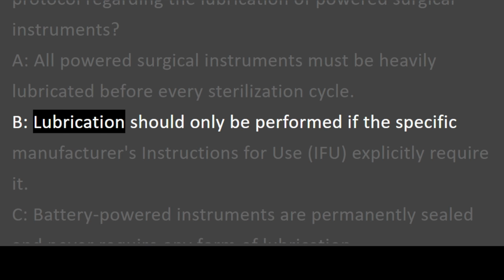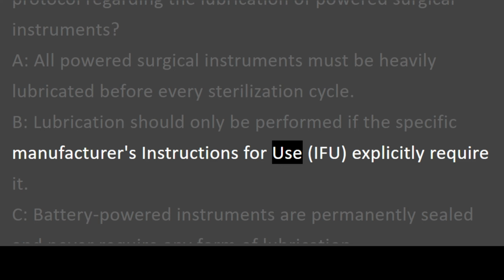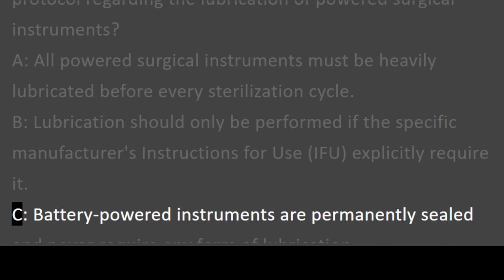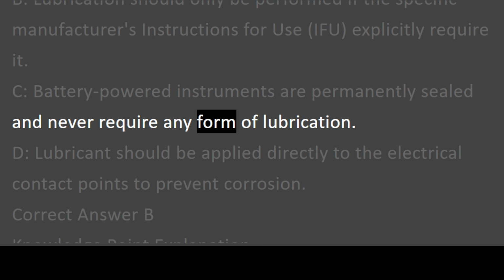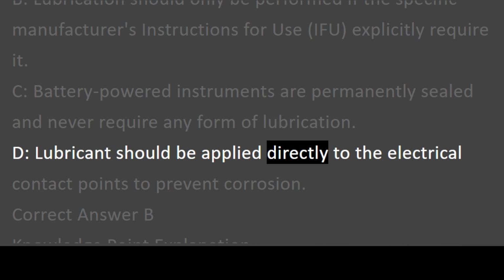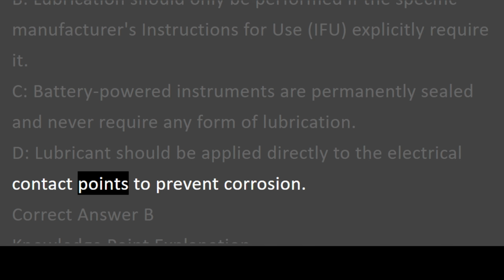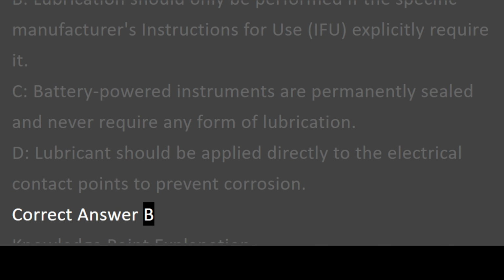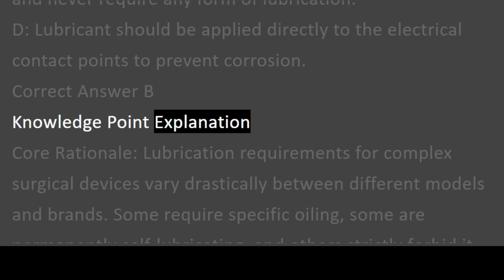B. Lubrication should only be performed if the specific manufacturer's instructions for use, IFU, explicitly require it. C. Battery-powered instruments are permanently sealed and never require any form of lubrication. D. Lubricant should be applied directly to the electrical contact points to prevent corrosion. Correct answer B. Knowledge point explanation.